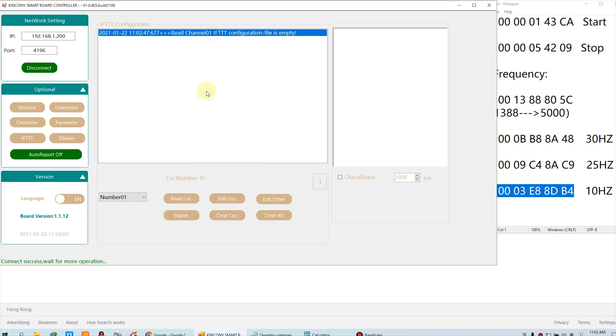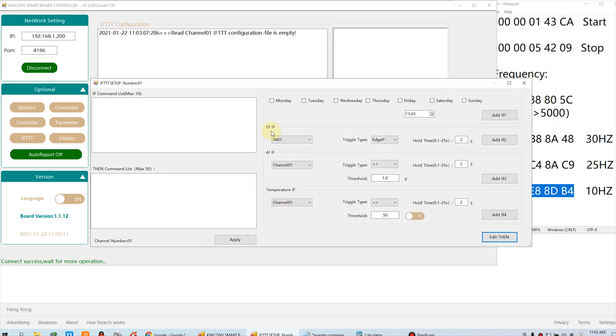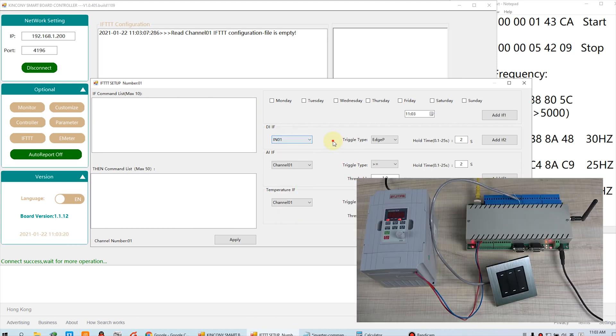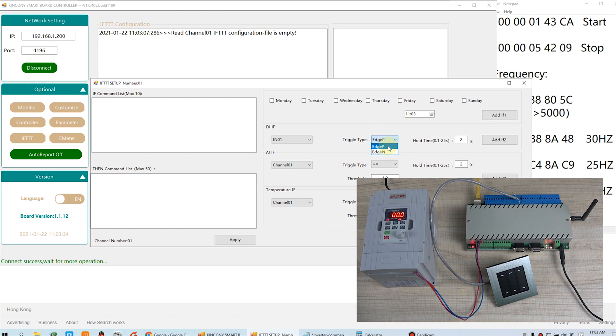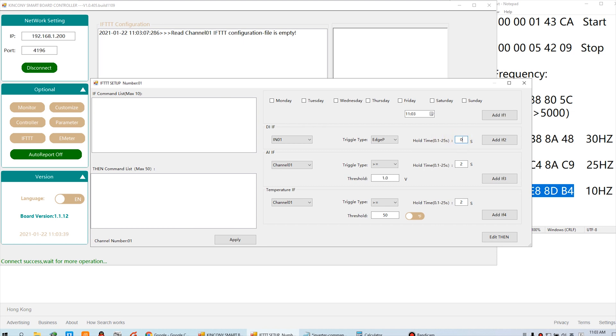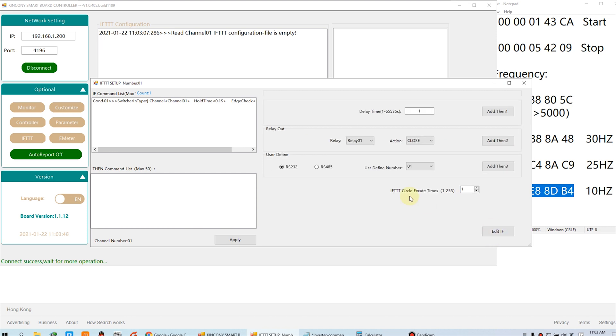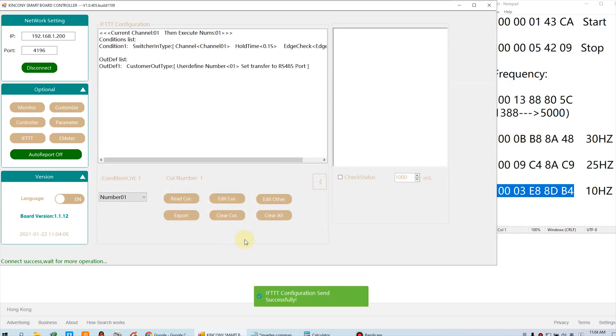Now we go to the IFTTT function — now it is empty. I can create IFTTT command number one. Just edit. Because I have used the switch panel, this is for digital input, so I can define input one — just key one. This is input one, and this is for the hand — the hand is on. When I press and hold for 0.1 second, we will trigger. We can add this function, and now go to 'then'. We can do this: RS485, send the command to the RS485 port by command number one — that is the start command. We can add the command, and apply. Okay, you can see the command is set.